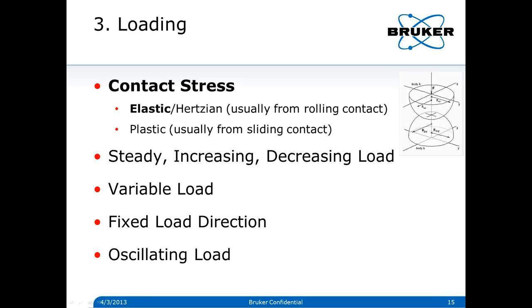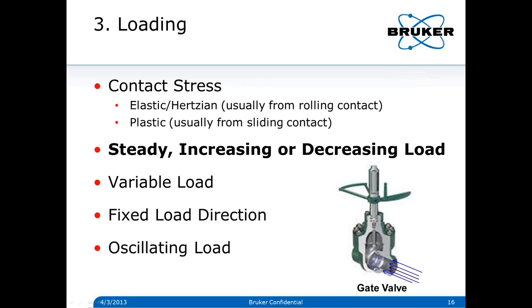Loading is our third area of interest. What is the contact stress — is it elastic? If so, we can do Hertzian calculations, available online and on our Bruker software. If it's plastic, that's usually from sliding contact, and you can calculate the stress from the area and the load. The stress can also be steadily increasing or decreasing — for a gate valve, depending on whether it's opening or closing, we would have a variable load: increasing as the delta pressure across the valve builds up as you close it, decreasing as you open it.